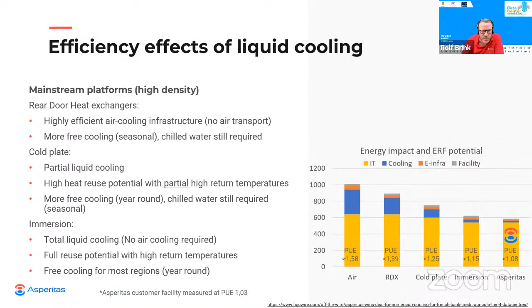This also means that immersion often enables year-round operation with free cooling strategies. A small note should be added though, that everything I'm explaining about these technologies is dependent on the IT platform, which needs to support the same elevated temperatures and heat production. Some HPC and supercomputing operators would therefore prefer to stick with chilled water circuits if that enables higher clock speeds, for example, while mainstream enterprise applications often have a greater focus on efficiency and high temperature operation.